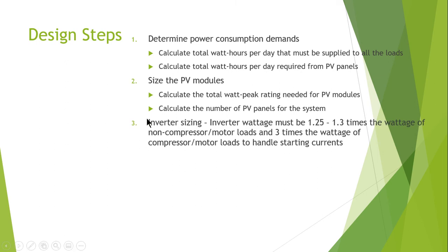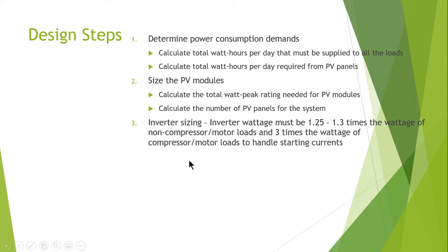The third step is to find out the inverter size — what size of inverter should be capable of handling the load requirements. We must take into consideration that the inverter wattage must be 1.25 to 1.3 times the wattage of non-compressor motor loads, and 3 times the wattage of compressor motor loads, in order to handle the starting currents.